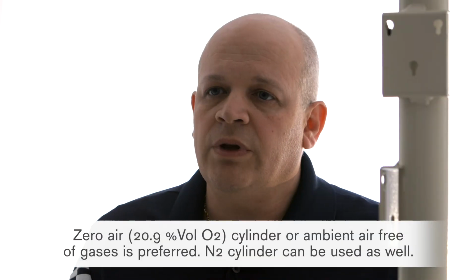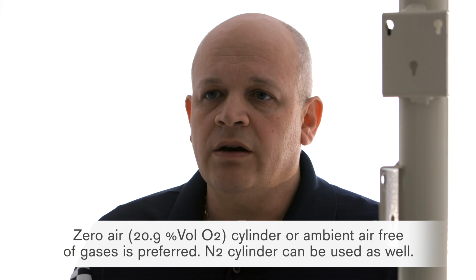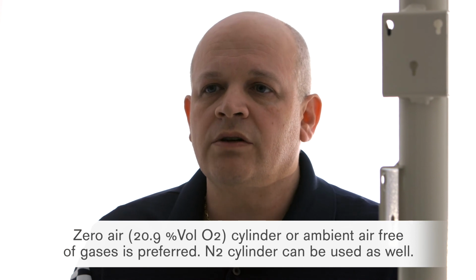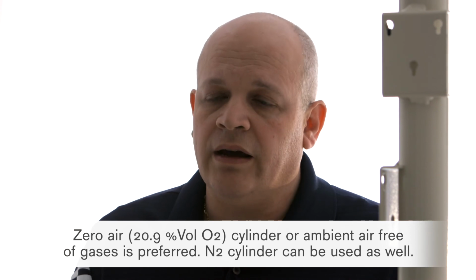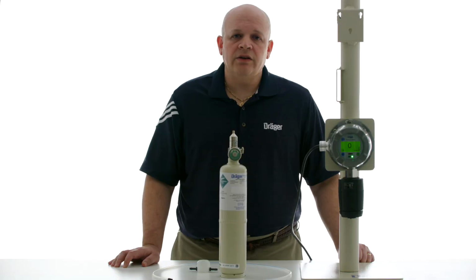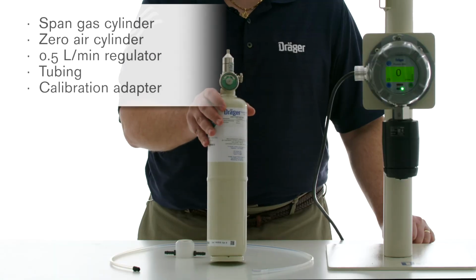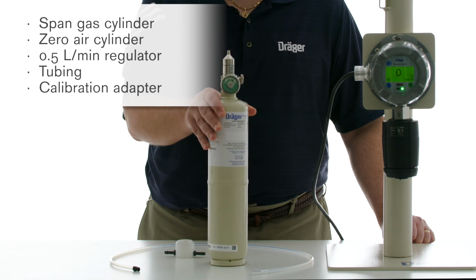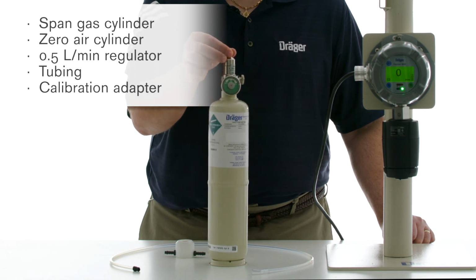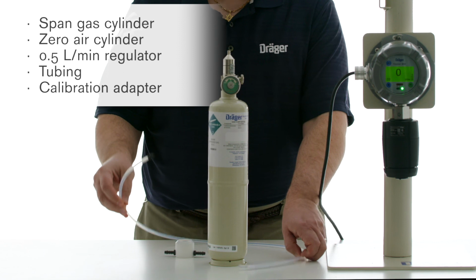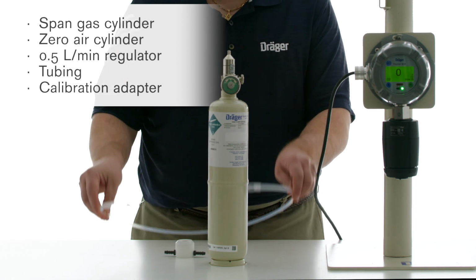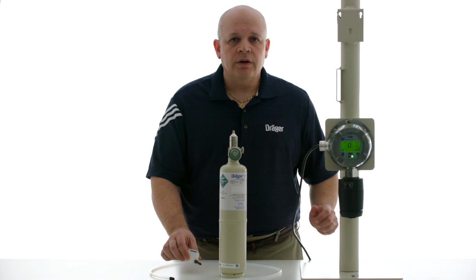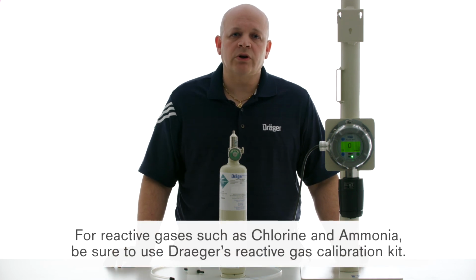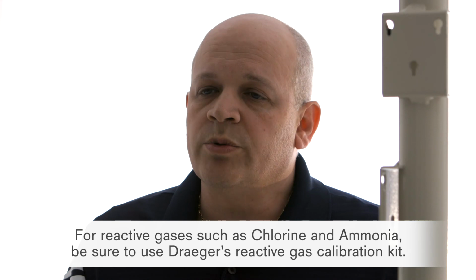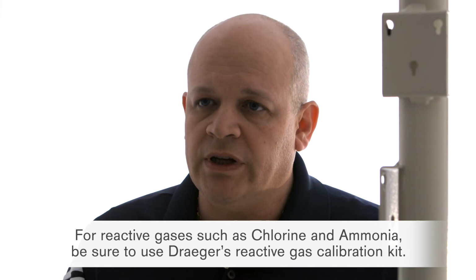The zero gas can be either nitrogen, zero air with 20.9% volume oxygen, or fresh air or ambient air. The devices that you need to calibrate are a span and zero cylinder, a 0.5 liter per minute flow regulator, calibration tubing, and a calibration cup. If you're using a reactive gas such as ammonia, please be sure to use our reactive cal kit. Also, please be sure to read the manual before proceeding.